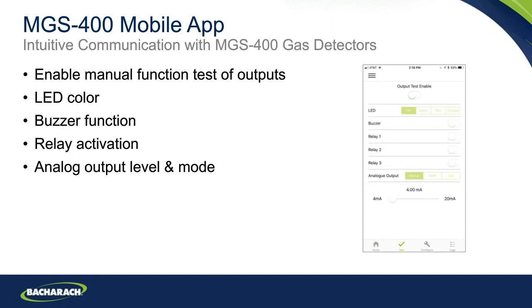And one of the key things here then again is the output test mode. We've got a manual functional test here to ensure that things such as the audible and visual alarms are functioning as they should, relays are activating and connected properly to things such as the horn strobes, the mechanical ventilation that we've spoken about. And you can adjust the analog output level and mode here as well to provide, again, the functional test if that's in use.